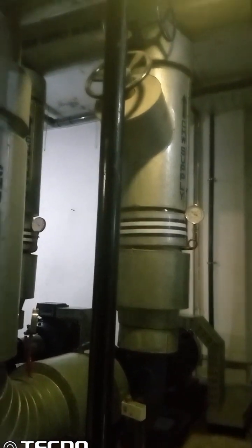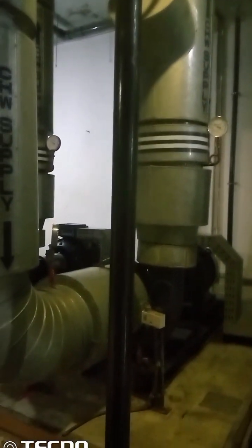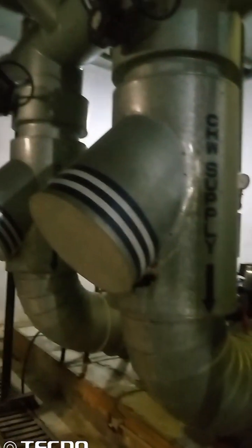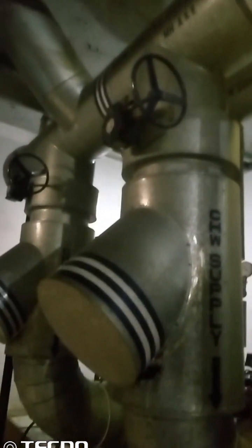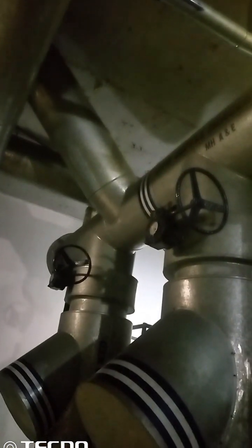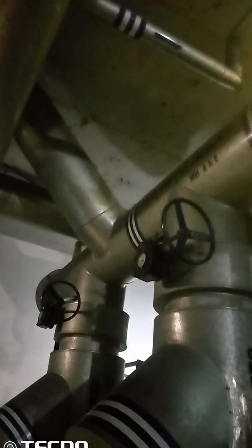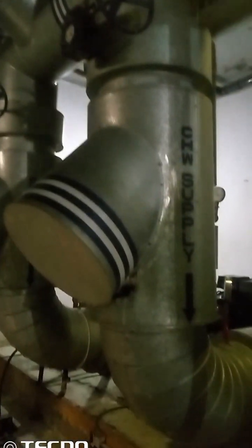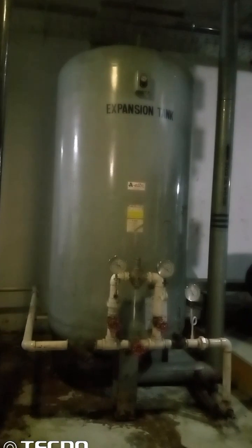I have explained 3 types of pumps in the plant room. The first one was the condenser pump, then we come to the primary pump, after that we come to the secondary pumps. What are the uses of these pumps? We will discuss them in a couple of seconds. But before that, one thing we need to discuss is the expansion tank in the plant room.